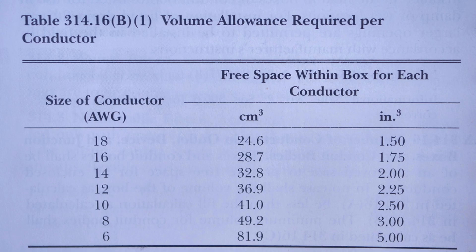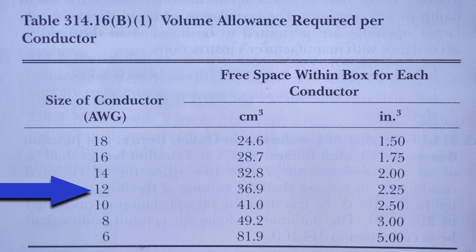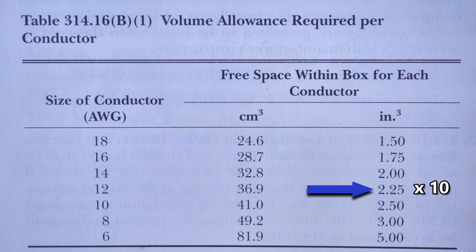We'll start at table 314.16B1 in the 2023 NEC, volume allowance required per conductor. This is the size of conductor in AWG. We find that the cubic inches per 12 gauge conductor is 2.25. We have 10 of these 12 gauge conductors, so we multiply this by 10.